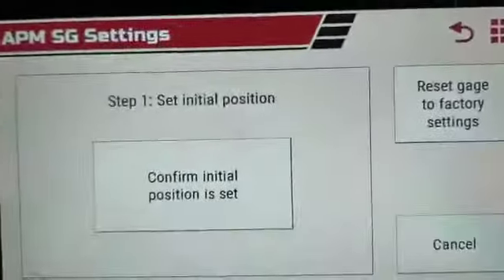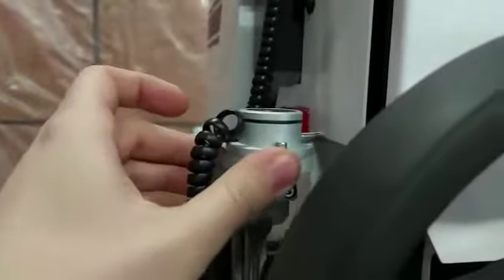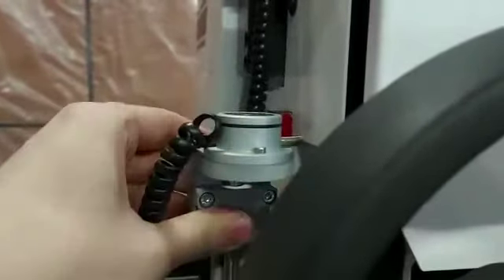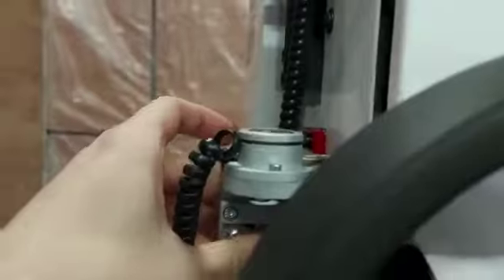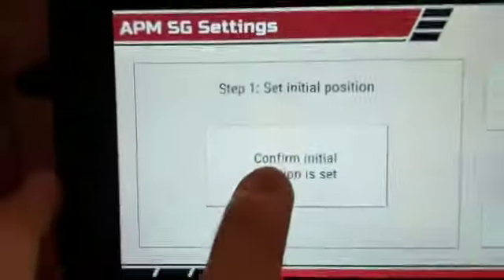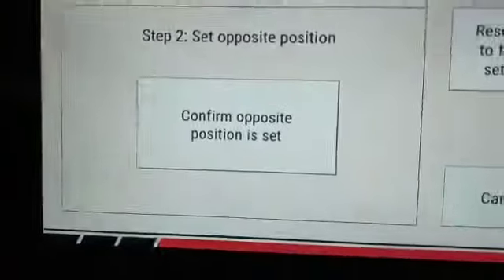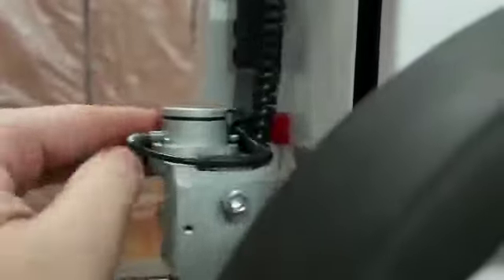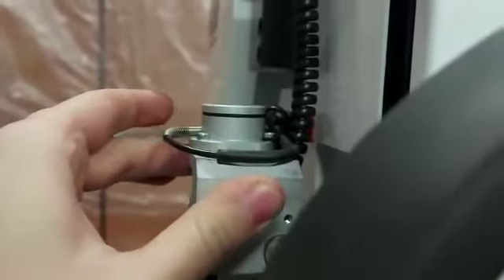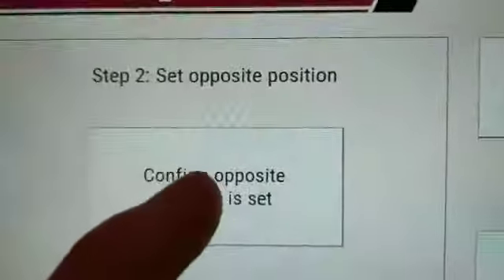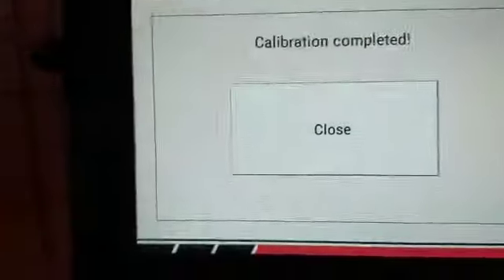So this begins the process of calibrating the inclinometer. First thing you should do is set the inclinometer in such a position that you can turn it 180 degrees. So I will prefer to set it so that it's just facing me. And then you click Confirm the initial position. And now all you have to do is just do the exact same thing, turn it 180 degrees. So turn it 180 degrees, you can use a protractor to be exact, and then confirm the opposite position is set on the screen. And your calibration is complete.